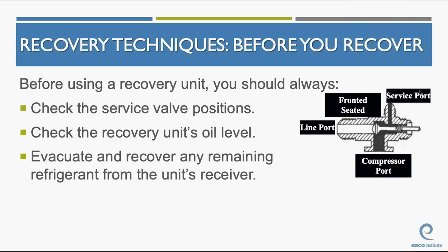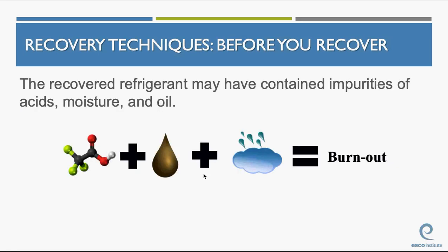The older recovery machines, the ones that weighed a ton, had their own receiver in them, and you used to have to make sure all the refrigerant was out of that as well. For the yellow ones and the newer ones, you don't even have to worry about that anymore. Recovered refrigerants may have contaminated impurities of acids, moistures, and oils. Make very sure that you've recovered all of the moistures and all of the oils out of the machine. Even if you have to flush it with nitrogen, make sure that machine doesn't have contaminants in it, because if you've had a burnt out compressor, you're going to have a lot of acids and moisture in that system.